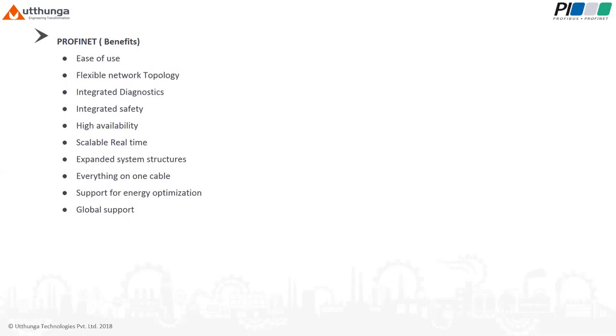Support for energy optimization. With the PROFIenergy profile integrated in PROFINET devices, the energy used in an automation system can be measured using a standardized method and controlled by selectively switching functions on and off without adding additional hardware. This is actually very useful in plants to conserve energy, because plants can go for shutdown if they are not working at times and go for some short pauses also.